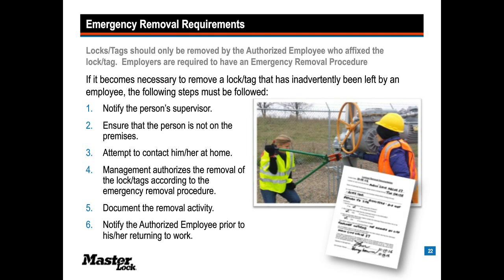As odd as it sounds, there have been a number of fatal and critical accidents that have occurred simply because a person's lock was cut off when they were not aware that it had been done. They did not do their due diligence of checking and verifying zero energy before they started work again, never checked to see that their locks were still in place. They began work and the machine was able to start up and do the damage that it did. So this requirement of OSHA is based in real-world experience of these accidents taking place.